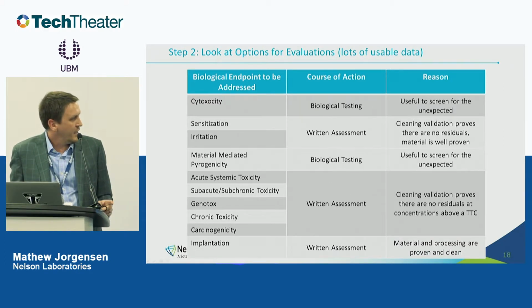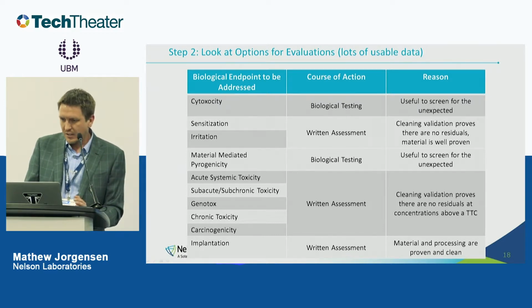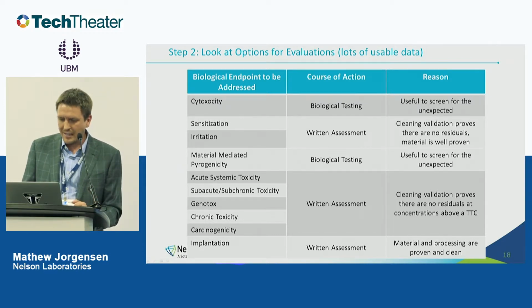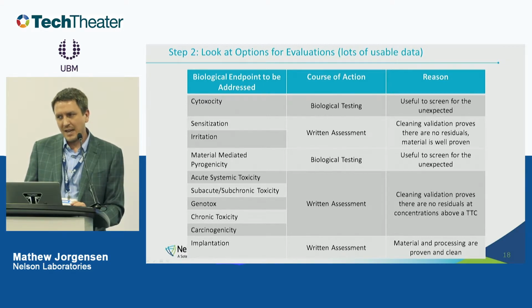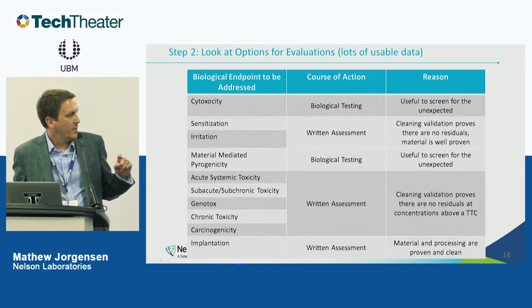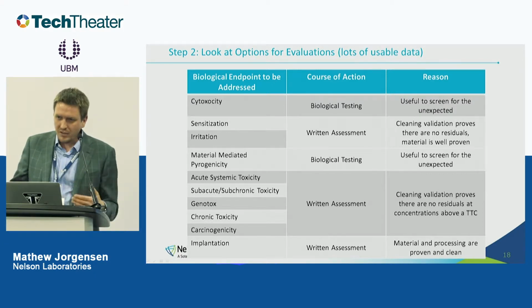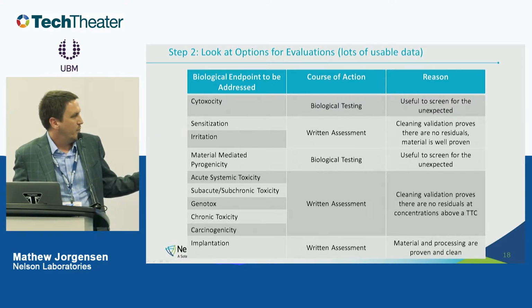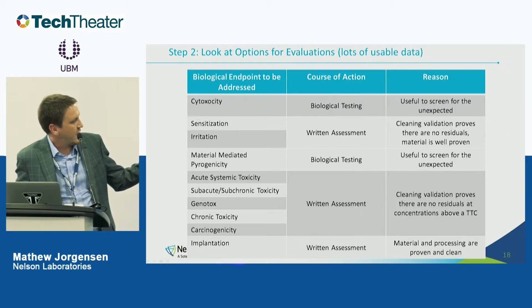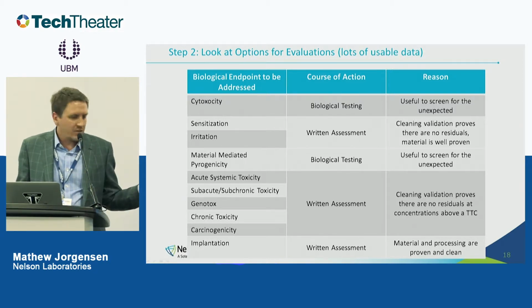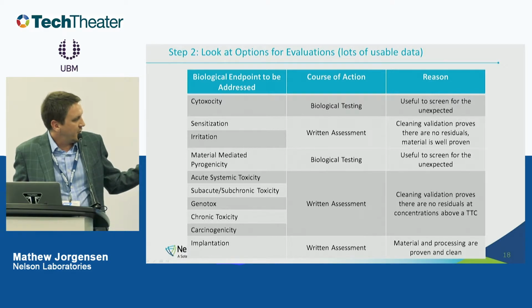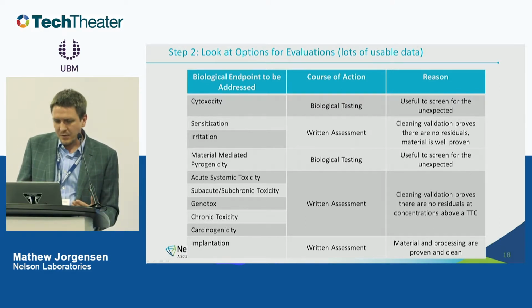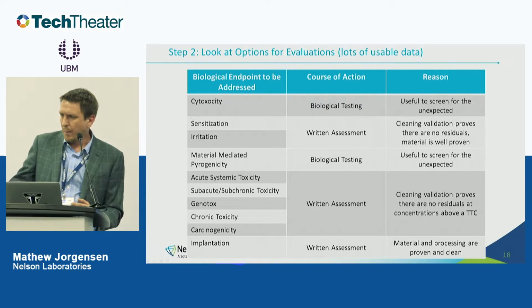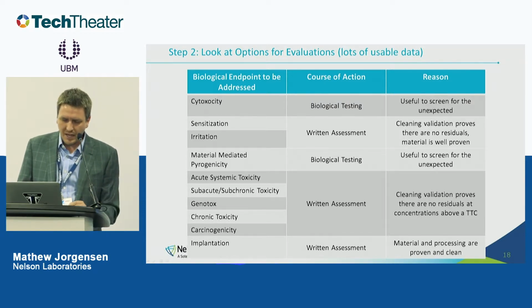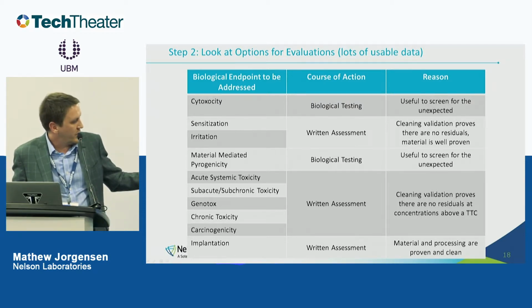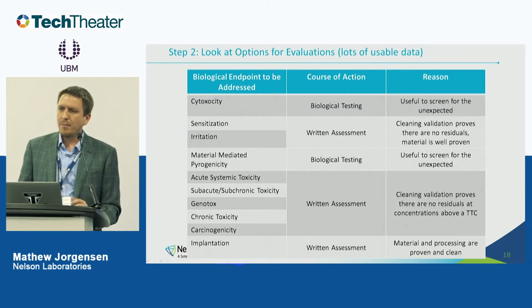On the other hand, if they have really good information, lots of usable data on hand, then this can really limit the amount of testing that needs to be done. So if they had lots of data and we were encouraging them to dig through what they've been given from their suppliers and stuff, then we still would run cytotoxicity testing, but sensitization and irritation, we could do a written assessment for that. MMP, they would still be doing probably as part of their sterilization plan anyways. And then for all of the others, we could make a written assessment based off of the data that they have.